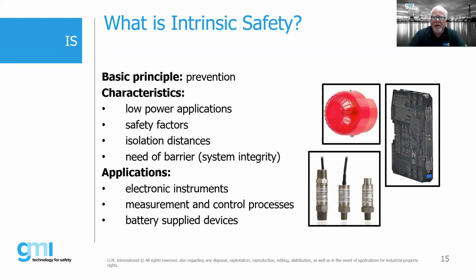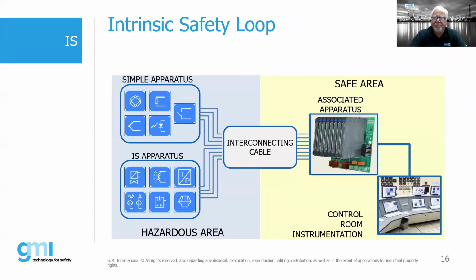So generally speaking, you really cannot make a motor starter intrinsically safe. Lighting, for example, general purpose lighting or EX lighting, is not intrinsically safe. However, instrumentation devices and signals, those types of devices, we certainly can make intrinsically safe. We have safety factors that are built in. There are requirements on isolation distances between IS and non-IS. And of course, we also need a barrier, and that's part of our system integrity. And again, the applications are instruments, measurement and control process, and some battery supplied devices.